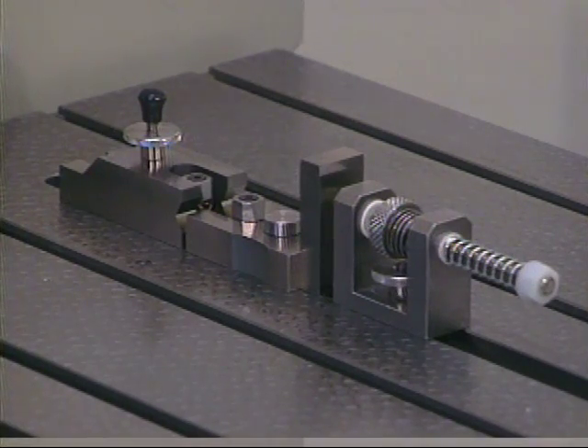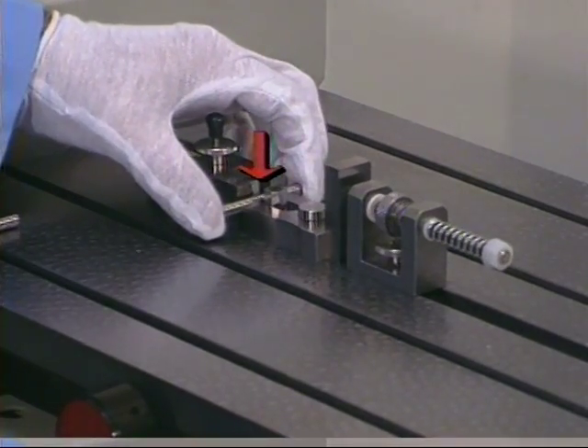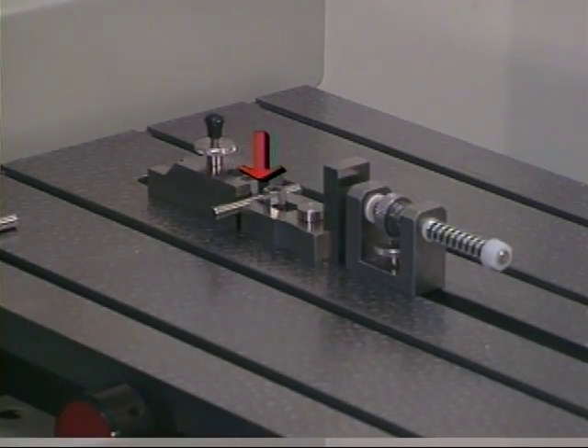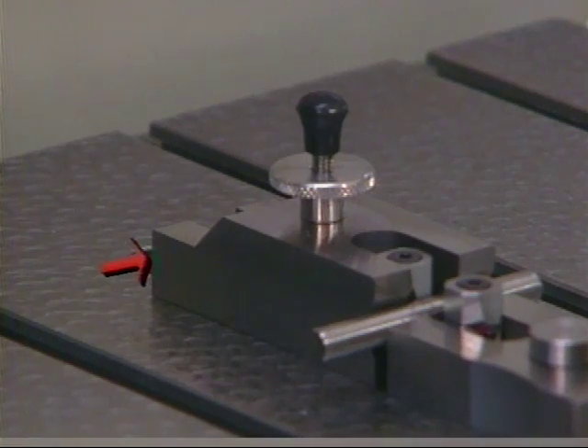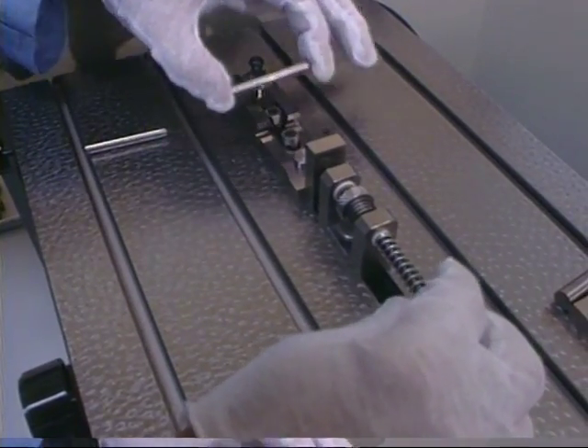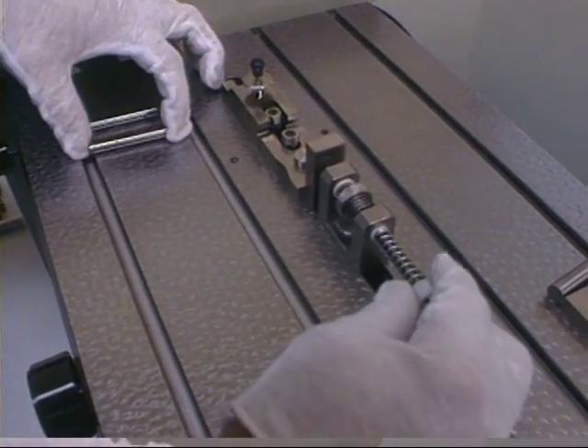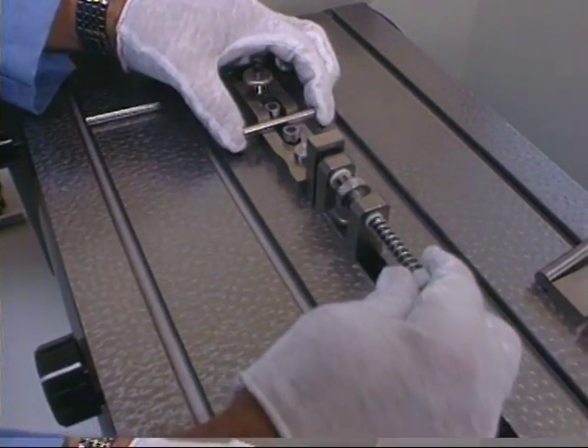Pin gauge calibration is accomplished by using a dual horseshoe clamp, a horseshoe and a probe positioner. The V-notch that holds the pin in the center allows measurement of the pin in different places. A small V-notch on the opposite end of the clamp accommodates smaller pins. The spring-loaded probe positioner allows you to quickly change your pin gauges.